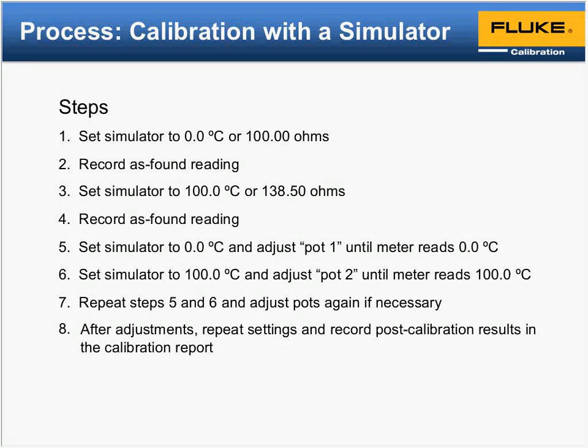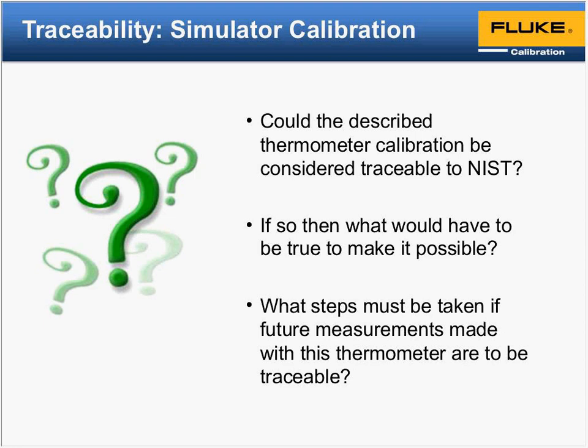So again, the pros of calibrating with a simulator, obviously it's very fast. Settings and the readings are fairly instantaneous. There's not a whole lot of stabilization time. But the only consideration is your ambient. So if you're in a room extremely hot or extremely cold, there might be some considerations around that basic unit specifications. Most of the time, these simulators are fairly portable. Even larger ones you can use with one hand. The other thing is that simulators use sometimes probes, or you can use different types of RTDs, and what we kind of touched on to be considered is that the probe here was taken out of the process on the electrical piece and calibrated.